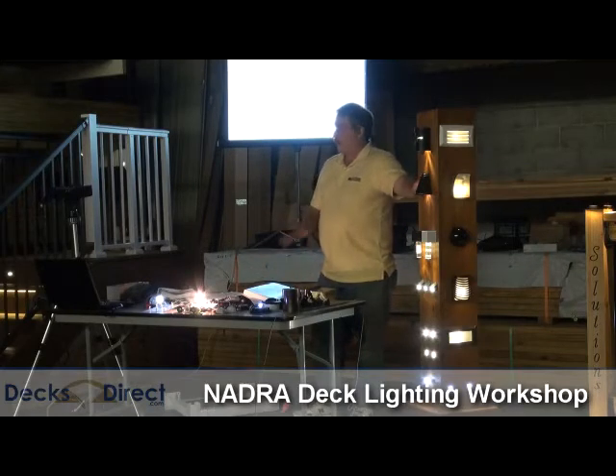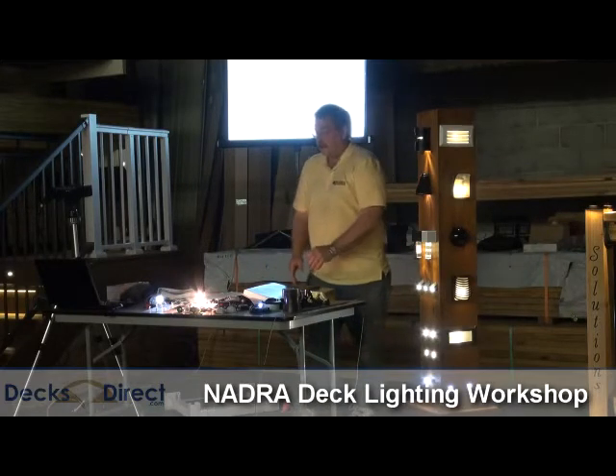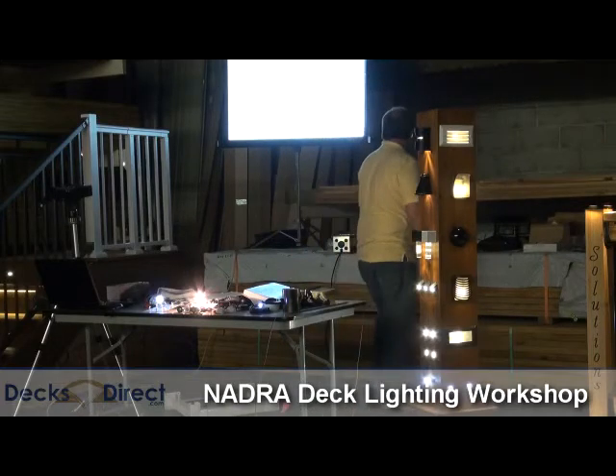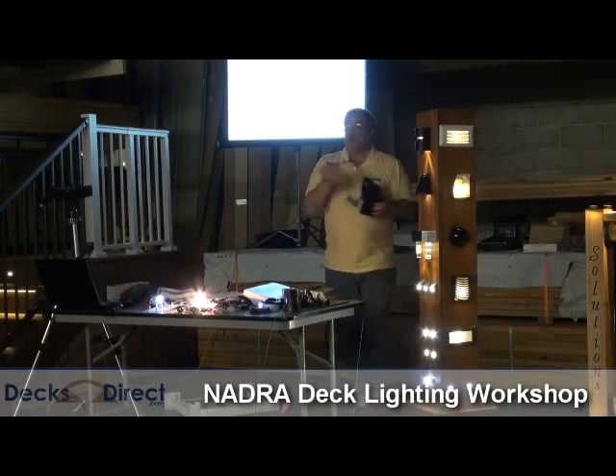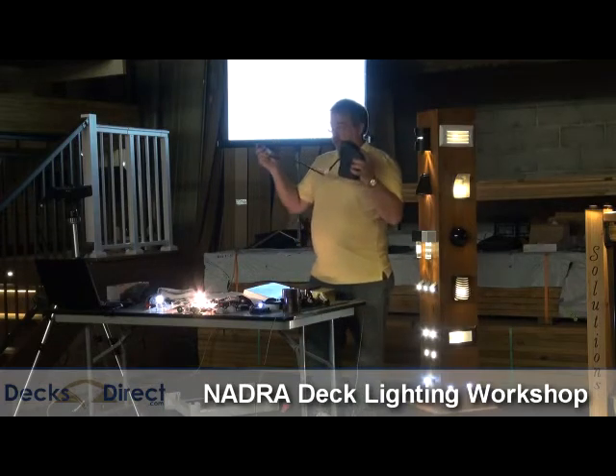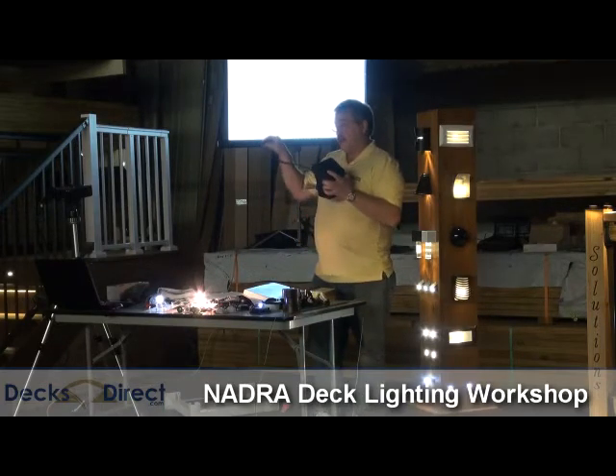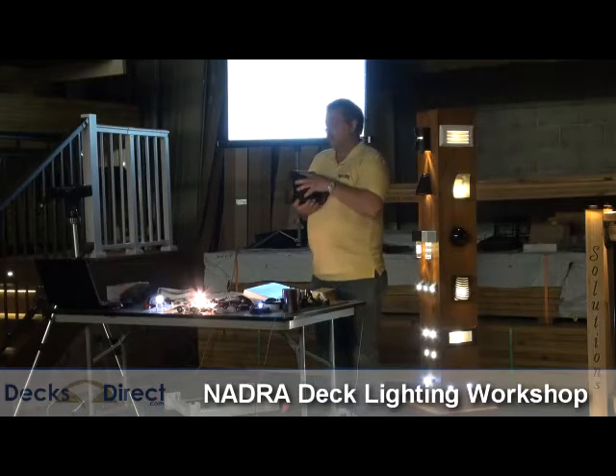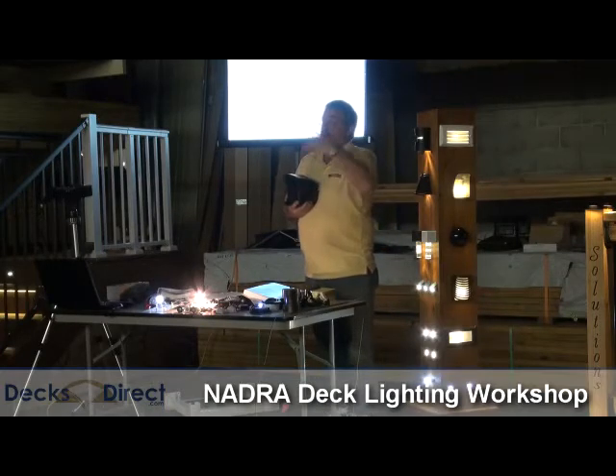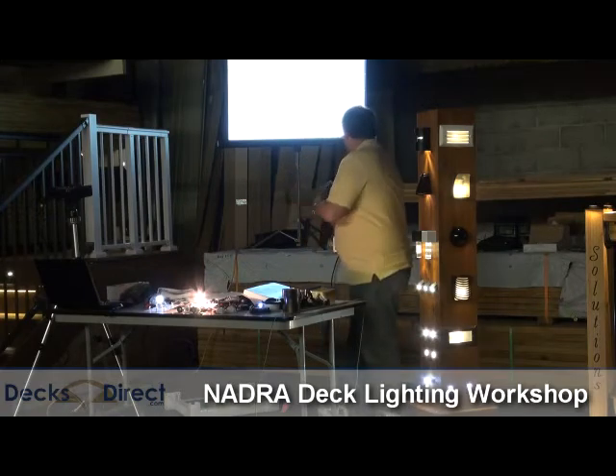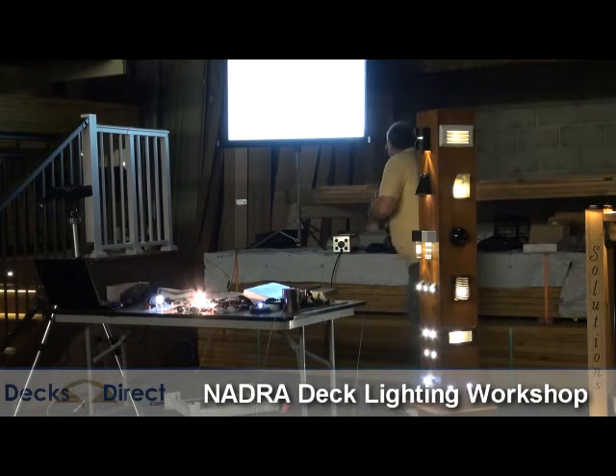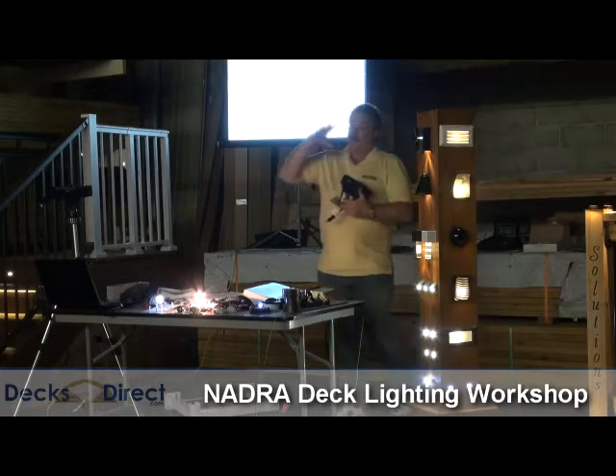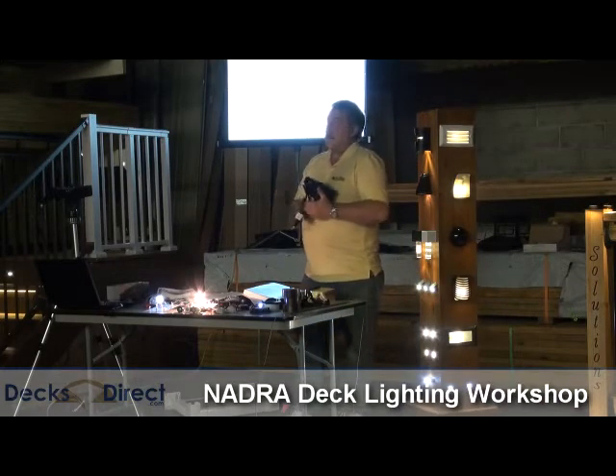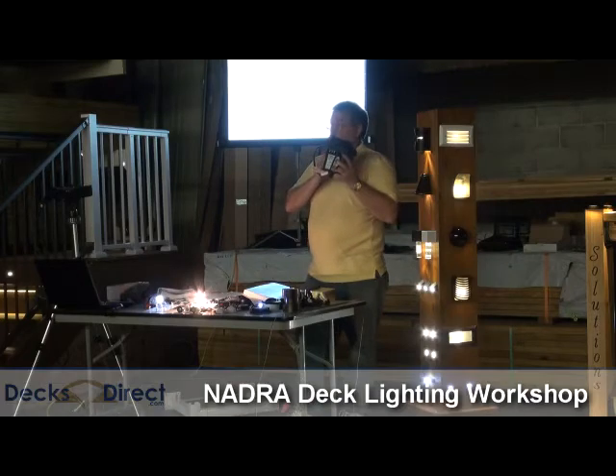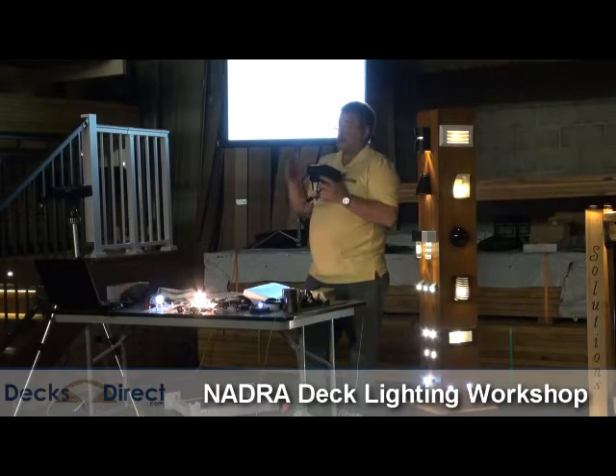Everybody says, well, they're low voltage. What could that possibly hurt? The explanation is these transformers that Blair brought in only have 2 prongs on them. They're non-grounded transformers. When you plug this stuff into a GFI outlet, you're converting the electric through magnets to another type of circuit. Even if they have 3 prongs, I saw one that he brought up had a 3-prong circuit on it, you have a different ground plane at your deck. When these transformers go bad, you get a short between the primary and the secondary coil, and you can put up to 600 volts across these lights.